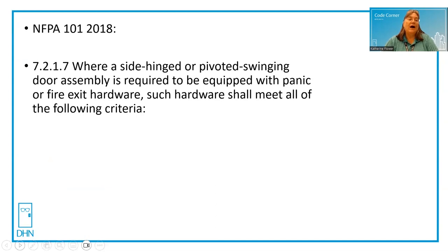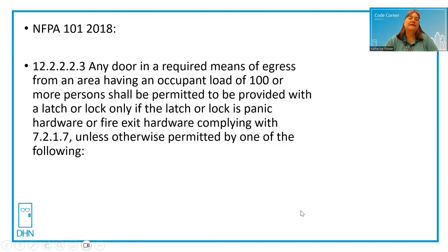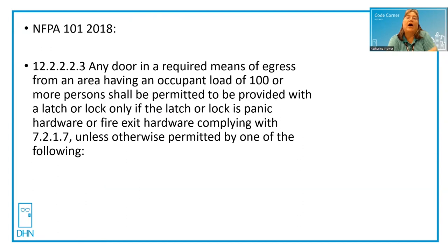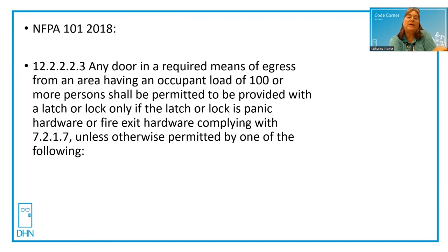And then you have to go to the occupancy chapter. Let's look at Chapter 12 for new assembly occupancies. Here's our reference to that fundamental Chapter 7: any door in required means of egress from an area having an occupant load of 100 or more persons shall be permitted to be provided with a latch or a lock only if the latch or lock is panic hardware or fire exit hardware complying with 7.2.1.7, unless otherwise permitted by one of the following — and it will list the exceptions.